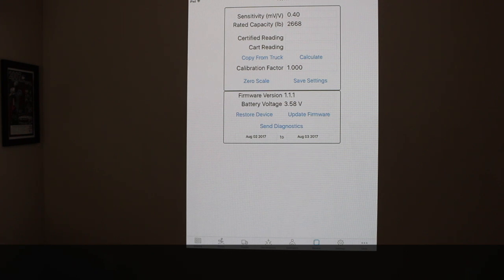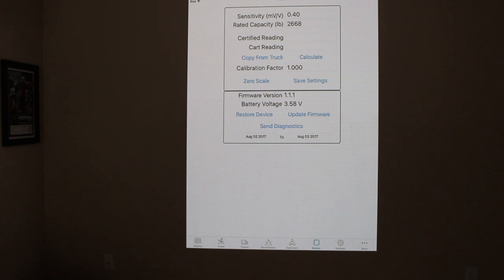I like to use a different method than this. I'll explain that after I explain the first way of doing it. Probably the little bit more complicated way is you could put the sensitivity at the sensitivity of the weigh bar. So if you look at the weigh bar and add up the rated capacity of each one. So if it's marked on the weigh bar and you can see that, you would take the capacity of the bar times however many bars there are. And then if it has a sensitivity labeled on there, you can put whatever sensitivity it would be. So an example would be if you do see, say, a sensitivity of 1 and then a rated capacity of 30,000, you have 3 bars, it'd be 90,000, for example, if you do see that.